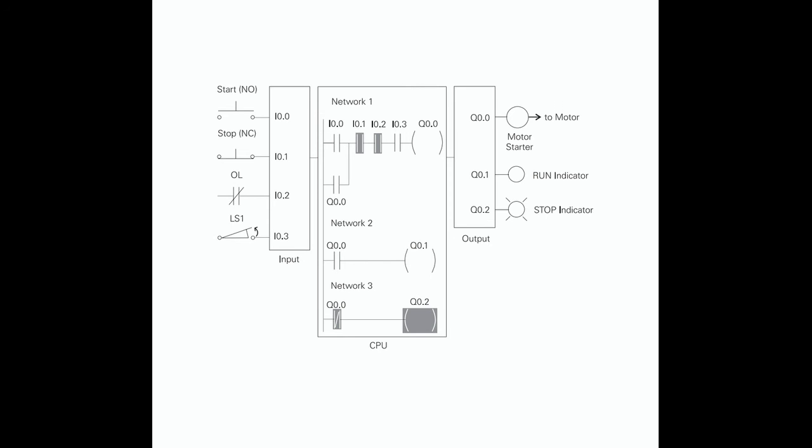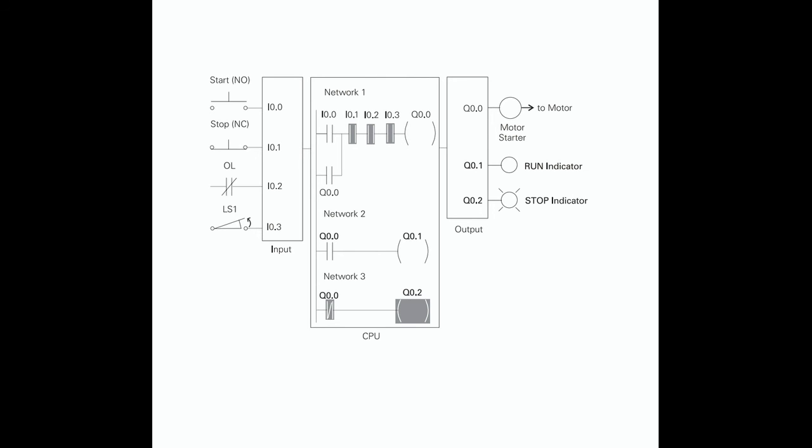Adding a Limit Switch: The application can be further expanded by adding a limit switch with normally open contacts to input I0.3. A limit switch could be used to stop the motor or prevent the motor from being started. An access door to the motor or its associated equipment is one example of a limit switch's use. If the access door is open, the normally open contacts of LS1 connected to input I0.3 are open and the motor will not start. When the access door is closed, the normally open contacts on the limit switch LS1 are closed, input I0.3 is now on (logic 1), and the motor will start when the start push button is pressed.